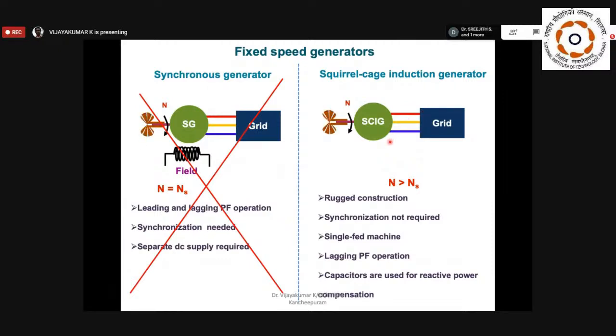So for reducing the reactive power drawn from the grid, people may use capacitor banks at this point. The capacitor banks will provide the reactive power support to the machine. Why is it always taking reactive power? Because the machine requires the magnetizing current, so it always takes reactive power from the grid. For that purpose, you can use the capacitor banks.